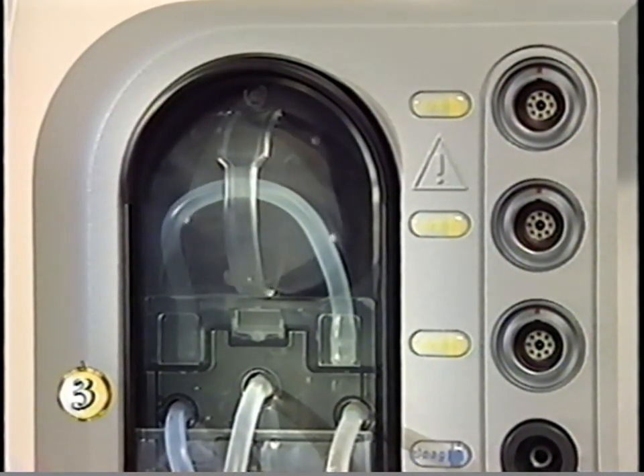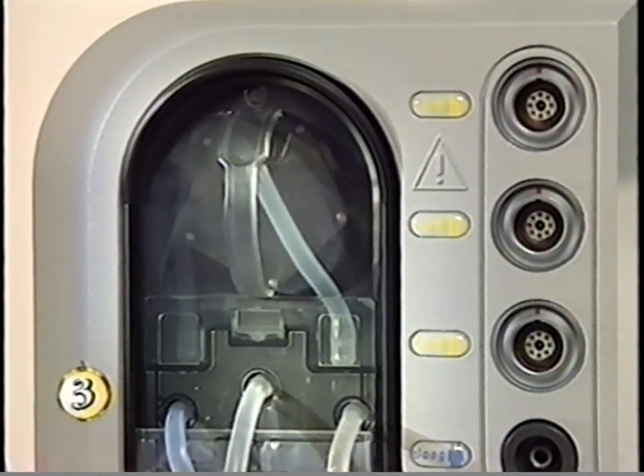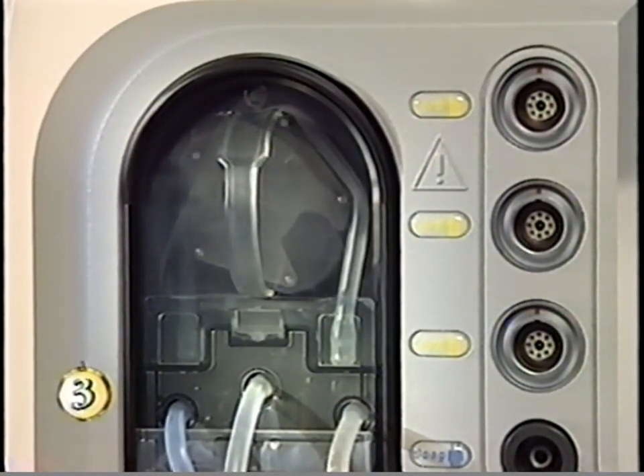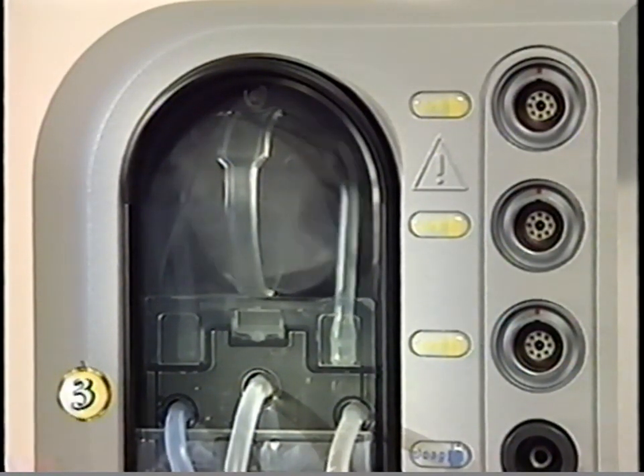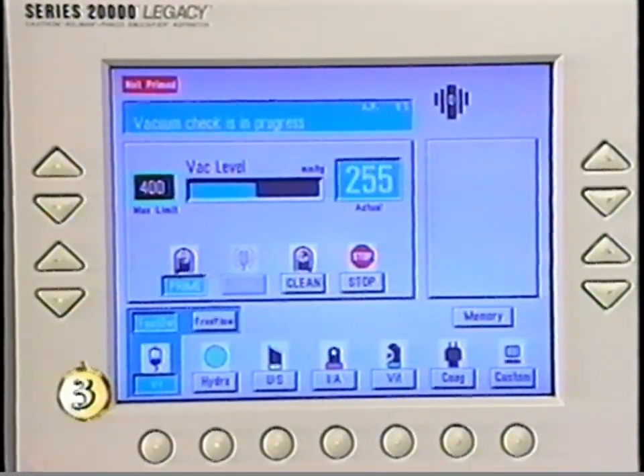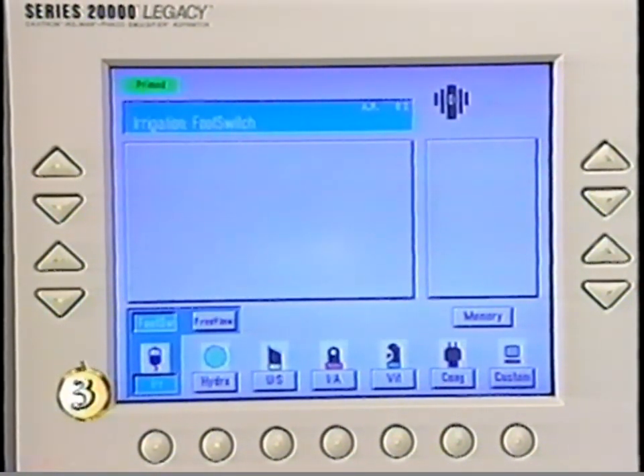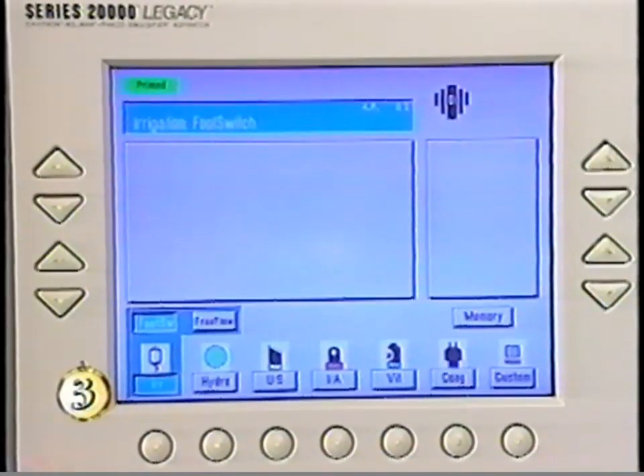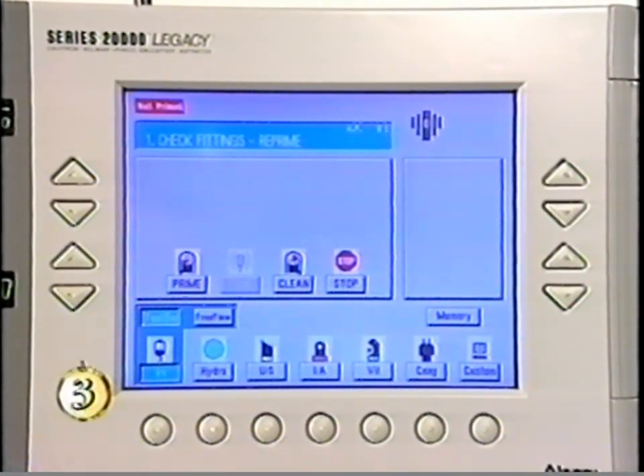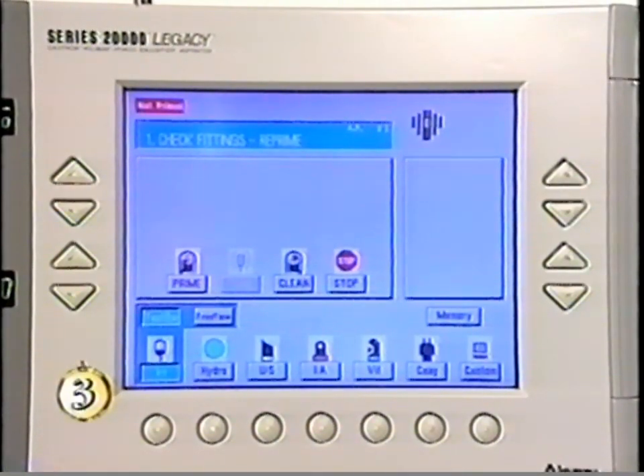Be sure the pump segment tubing loads properly in the initial seconds of the priming phase. You'll see the aspiration pump stop and restart during the test sequence. During the vacuum test, vacuum will build to 400 millimeters mercury. The vent test follows. After the vent test, the prime status indicator will turn green and text will change to primed. If the vacuum test fails and this message appears, reinitiate the priming sequence by pressing the test button twice. If this fails to eliminate the error message, consult the troubleshooting section of the operator's manual for corrective action.